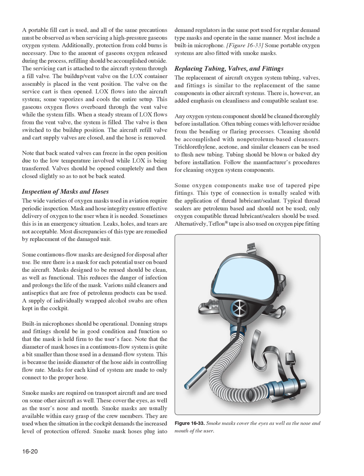The aircraft refill valve and cart supply valves are closed, and the hose is removed. Note that back-seated valves can freeze in the open position due to the low temperature involved while LOX is being transferred. Valves should be opened completely and then closed slightly so as to not be back-seated. Inspection of masks and hoses.